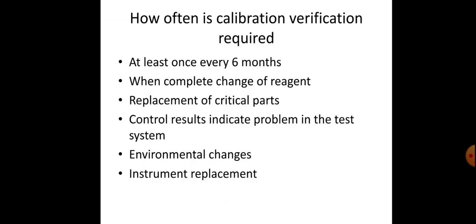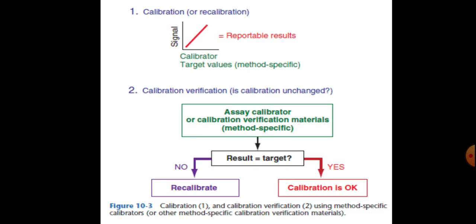So this is about the calibration verification graph. How often is calibration verification required? At least once every 6 months, and also when there is a complete change of reagent, replacement of critical parts, control results indicating a problem in the test system, environmental changes, or instrument replacement. This is the period where calibration verification is required.